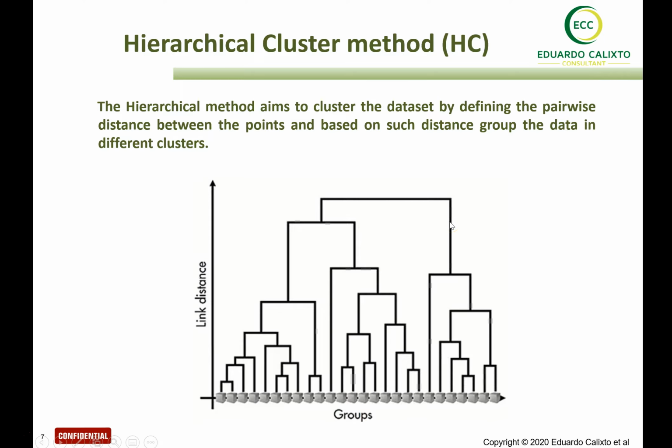That is a very high advantage for maintenance, because in the maintenance context, what we need to do is to group different equipment into different maintenance plans. Instead of shutting down the plants many times to find the best time to shut down one specific equipment, what we are trying to do is to group equipment that have similar remaining useful life or expected time to failure together. So by hierarchical clustering, I can make different shutdowns and consider three groups of equipment, such as in this last case that I discussed.